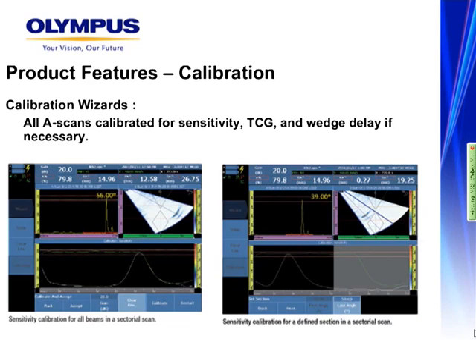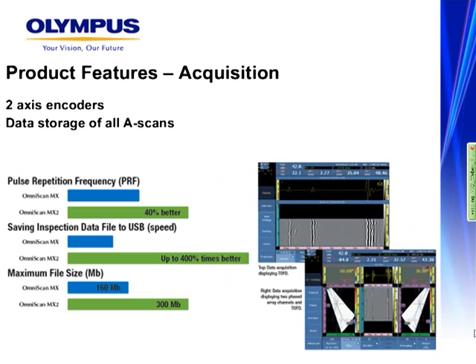Similarly to the group setup wizards, there are also wizards for calibration, including sensitivity, sometimes referred to as angle-corrected gain, TCG or DAC, wedge delay, and encoder calibration. These calibration wizards allow all focal laws and A-scans to be calibrated at the same time. Additionally, several enhancements to previous versions have been made to ease both theoretical TCG creation and extrapolating a calibration curve for two or more points. This is necessary to comply with existing codes and is an essential part of the inspection.